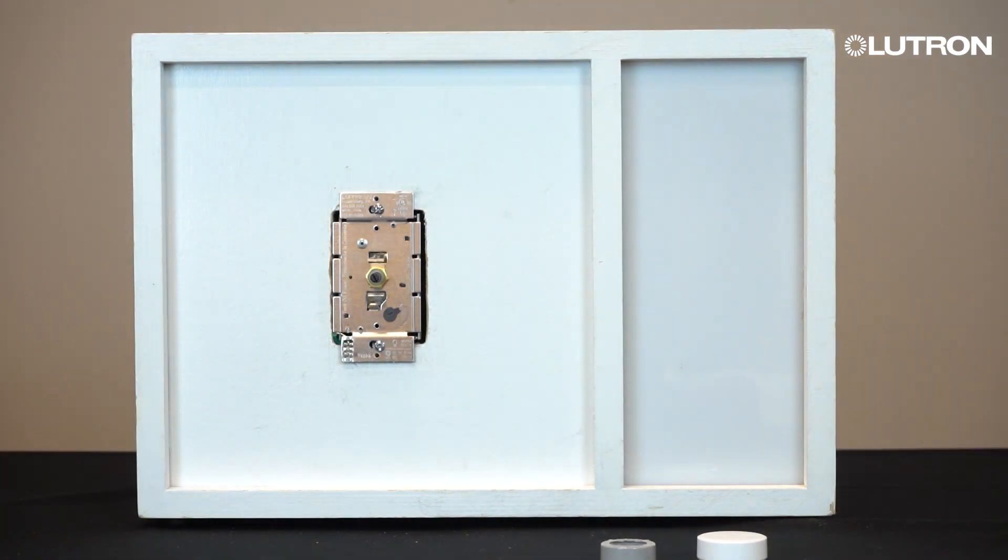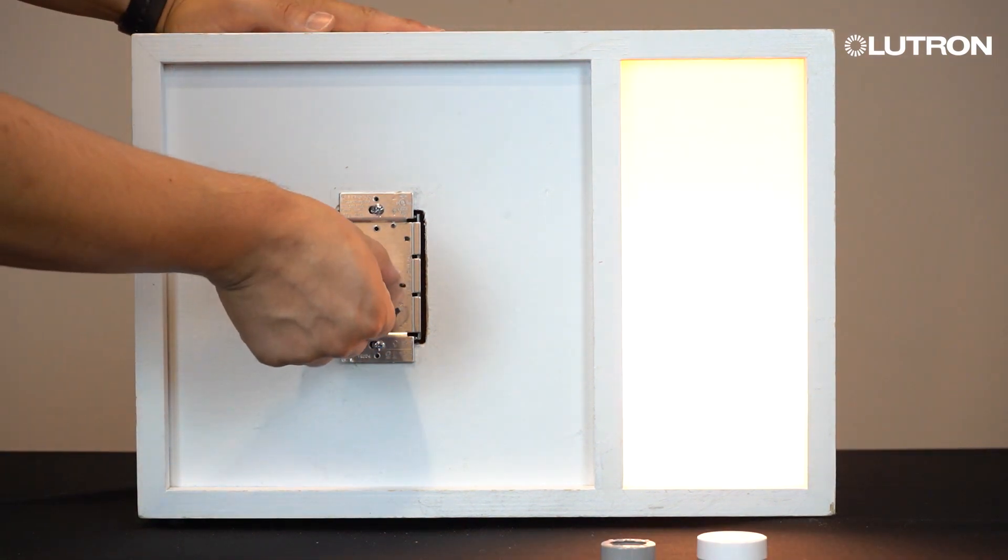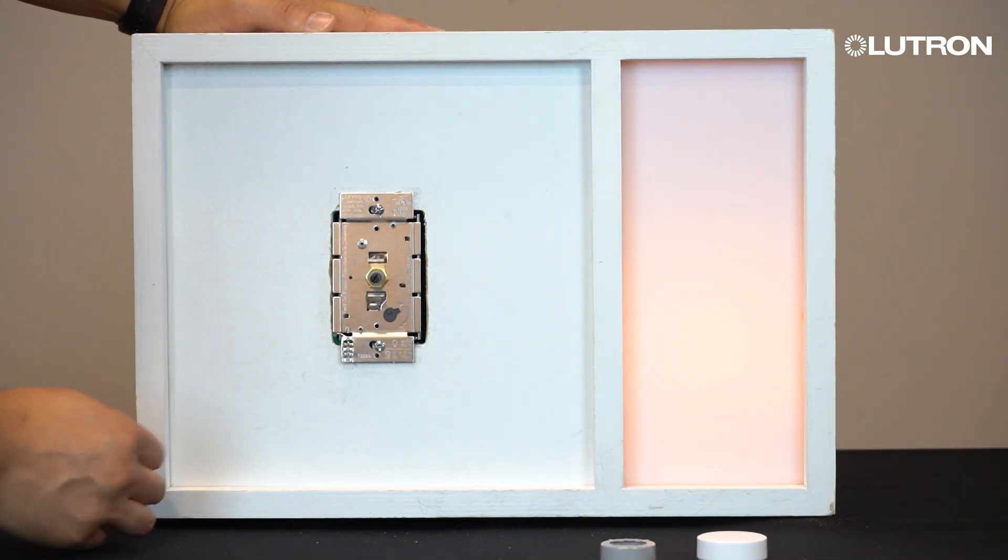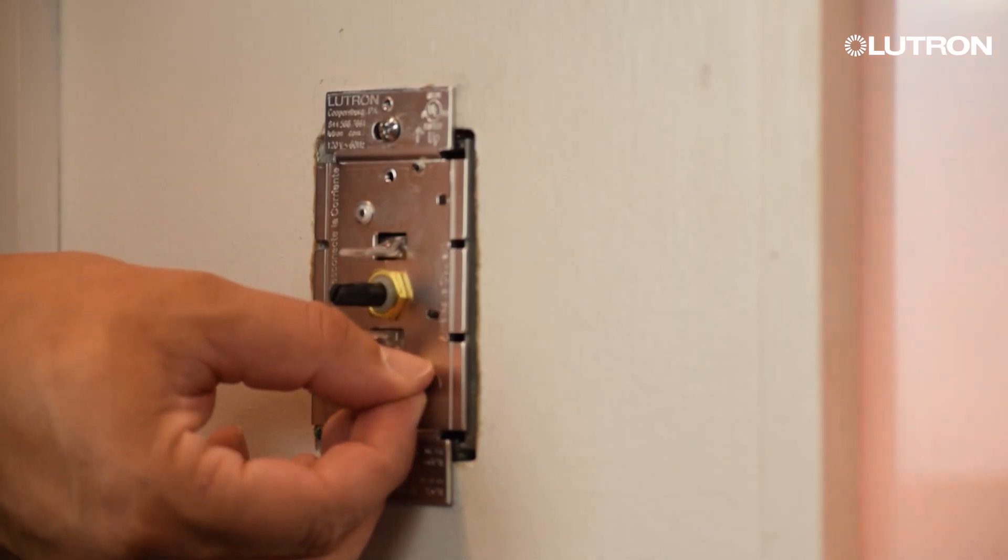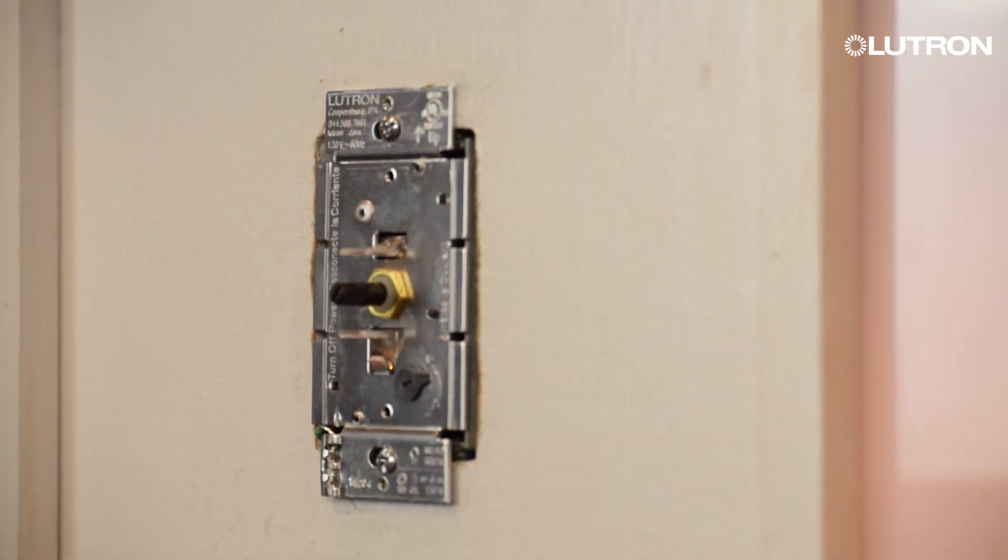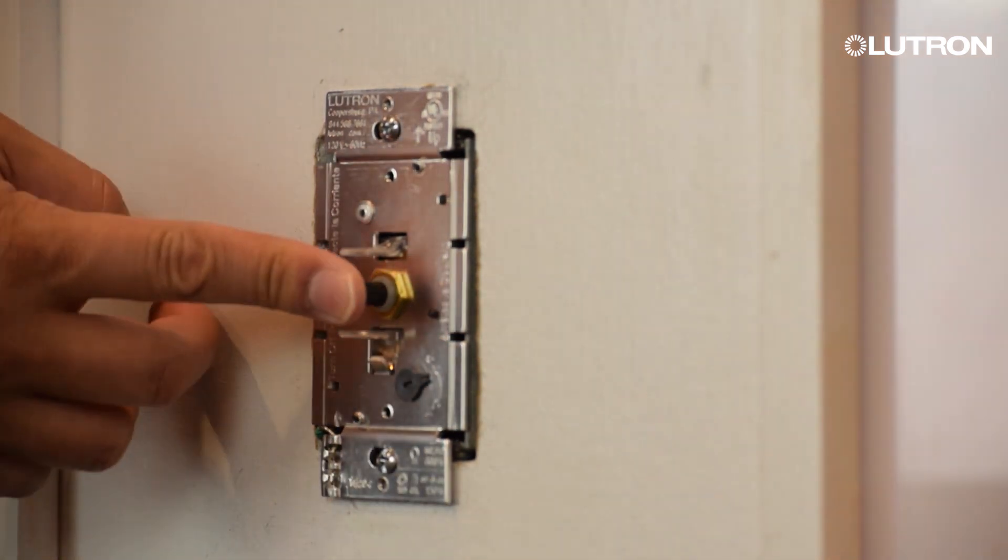Once the dimmer has been attached to the wall box, take this opportunity to adjust the low-end trim. Turn the power back on at the circuit breaker and then turn your lights on to their lowest level by turning the shaft counter-clockwise. You can now adjust the low-end trim of the dimming range with the black or blue dial to reduce any flicker or dropout the bulb may experience at low levels.